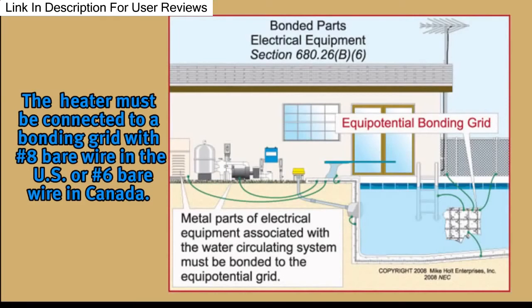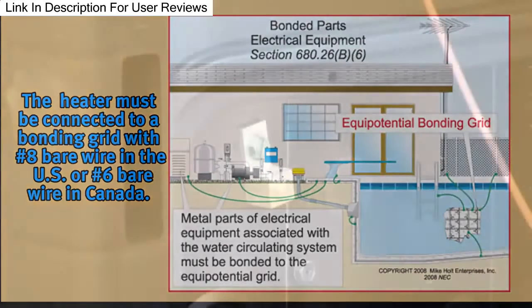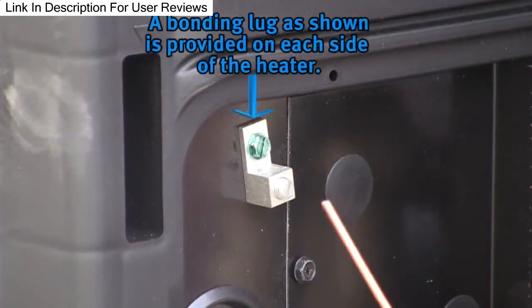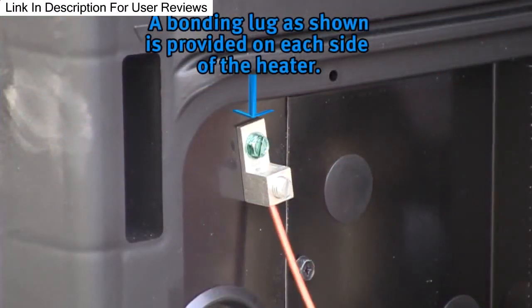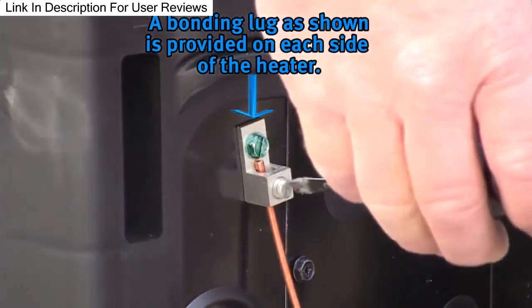The National Electric Code, NEC, and most other codes require that all metallic components of a pool structure, including reinforcing steel, metal fittings, and above-ground equipment, be bonded together with a solid copper conductor wire. This heater must be connected to a bonding grid with number 8 bare wire in the U.S. or number 6 bare wire in Canada. All Hayward heaters are designed for copper conductors only. A bonding lug is provided on each side of the heater to ensure that this requirement is met.